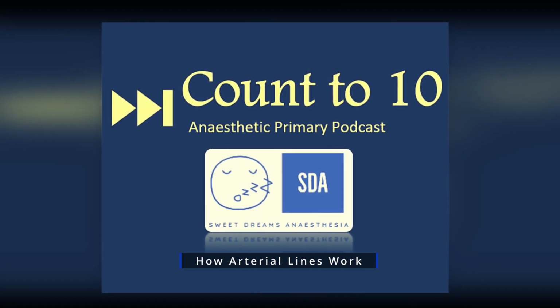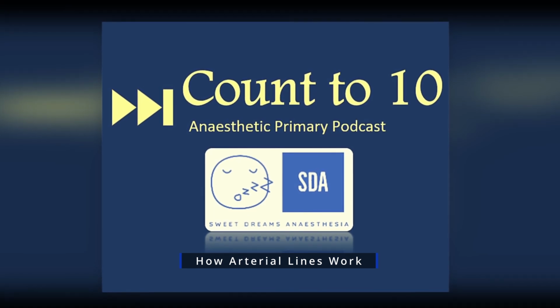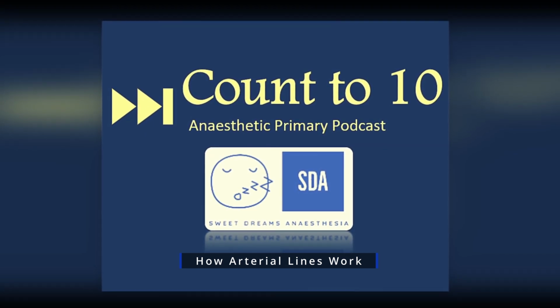But just to complete the components of an arterial line setup, when you go from your pressure transducer, you'll see two leads coming out of that. One of those leads is the continuation of the fluid-filled line, attaching to a pressurized bag of normal saline, which is normally pressurized at 300 millimeters of mercury. And what that's doing is achieving counter pressure to make sure that arterial blood flow doesn't enter the system. This bag can also be used to flush the line. The other cord coming out of the transducer is the microprocessor cord, which is then attached to a separate cord, which is part of our module, which interprets the signal and gives us our blood pressure reading.